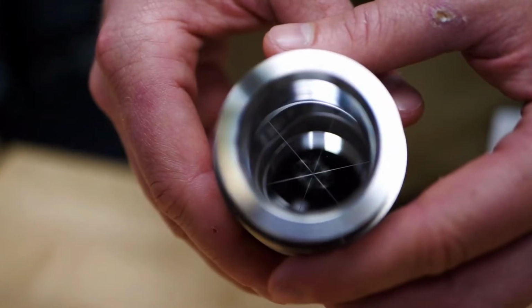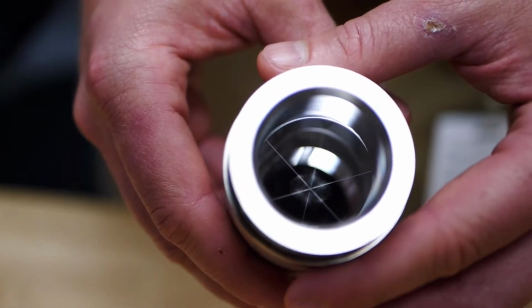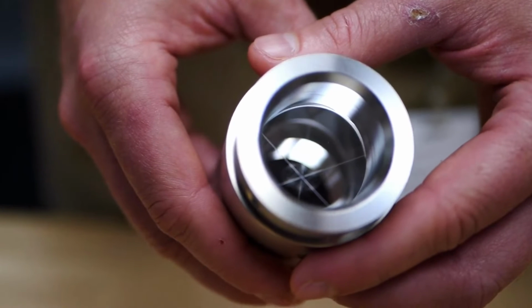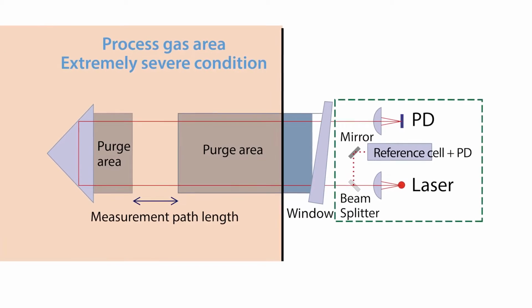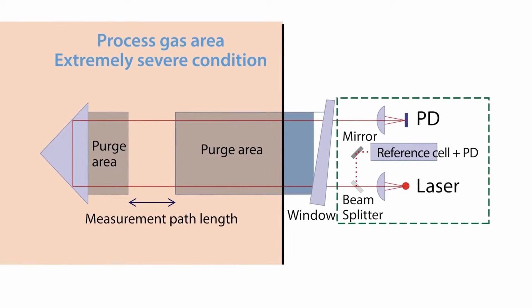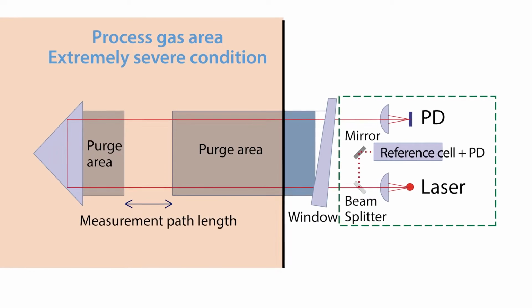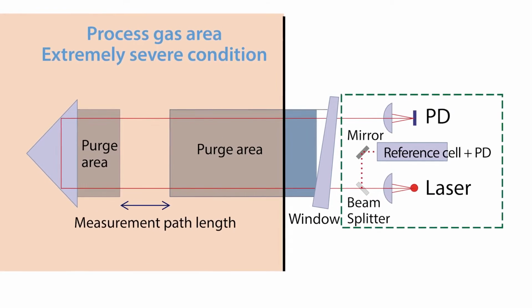Most spectroscopic analyzers have all the optical elements outside the hot process, protected by isolation windows. Only the optical radiation crosses the high temperature region. The TDLS8200, to the contrary, has optical elements immersed in the process to ensure a folded optical path with single-ended insertion. That brings along several engineering challenges.